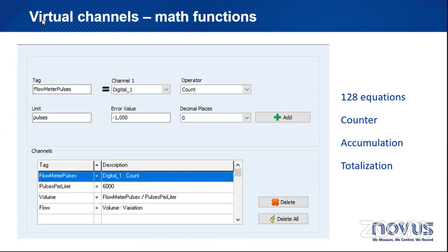So if I connected a flow meter to the FieldLogger's digital input that is generating pulses, and I read in the manual that this flow meter reads 6,000 pulses for every liter of water. So it's 6,000 pulses per liter of water, for example. In this example I brought here, I actually looked at a manual to do this. So what should I do?